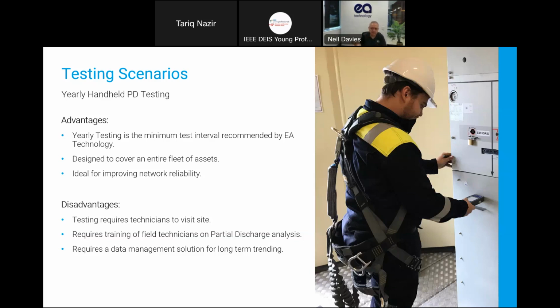Now, of course, the disadvantage of doing that is you're putting people in the field to test, so it requires trained, skilled people, which is time and money, of course. You need to get them trained so that they understand what it's doing. And if you're collecting all this data, you do need to be thinking about how you're managing that data and what solution you're putting in place for long-term trending. You'll get really valuable information as soon as you start testing, even on this basis. If you've got defects on the system that need to be taken off quickly, this will give you a very quick boost in network performance.